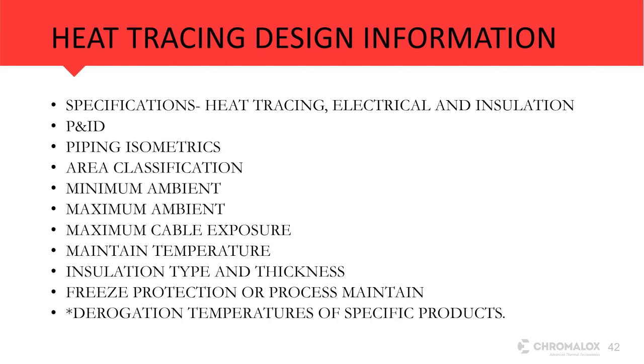Piping isometrics, area classifications, minimum ambient, maximum cable exposure, maintain temperature, insulation types and thicknesses, and is it a freeze protection or a process maintain? And also operating voltage. What operating voltage does the plant have? What operating voltage would they like for us to use?